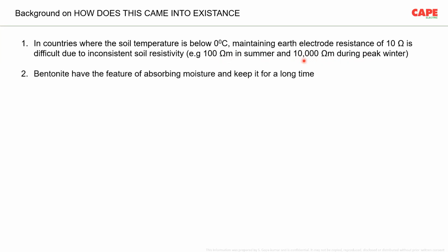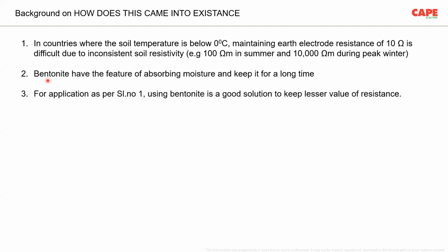It is drastically changing. Under that condition, if you use bentonite, which is nothing but the natural clay available abundantly in India, all around the earth electrode, the bentonite absorbs the moisture during summer and the rainy season, and keeps the moisture for a longer time. As a result, the area all around the earth electrode is a little bit wet, and the resistance we get is lesser. So for the application as per serial number 1, using bentonite is a very good solution to keep lesser values of resistance.